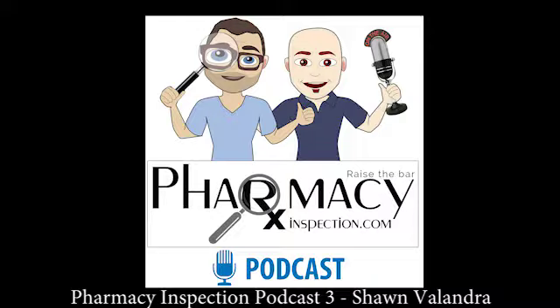Brian noted that the 'solution is dilution' mindset drove the old ISO standards — filling ceiling space with fan filter units to dilute, dilute, dilute. USP says those numbers aren't required. Even without pushing 60–90 air changes — which Sean and Brian commonly see on projects — you can still maintain your ISO standards at 35–45 air changes per hour.